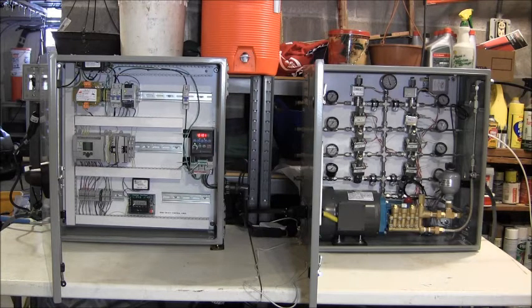Now this control assembly over on the left here does quite a few different things, but overall it does just a couple things when you look at it, and that is that this microcontroller here starts and stops the machine and actually drives the solenoids that you see, solenoid 1, 2, 3, 4, 5, 6, and we've got a couple spares down here. These 6 solenoids turn on and off depending on the demand, and then the water actually goes out the hoses and supplies the misting heads.